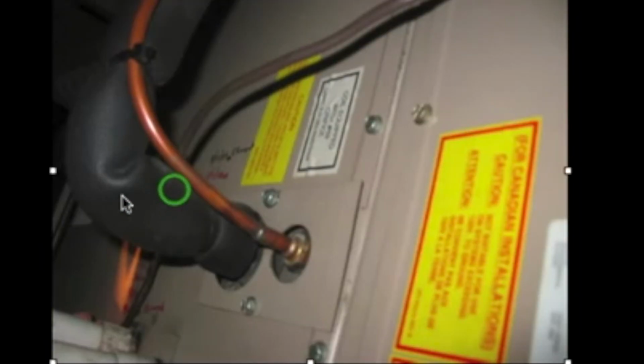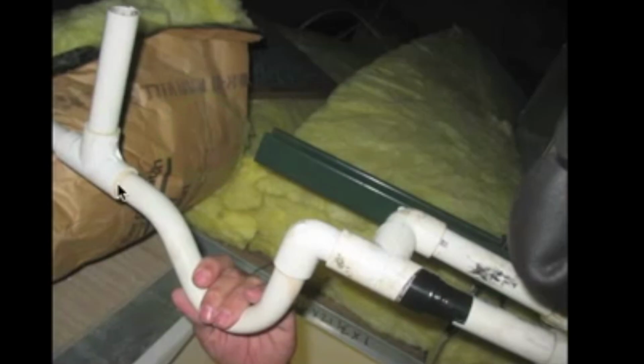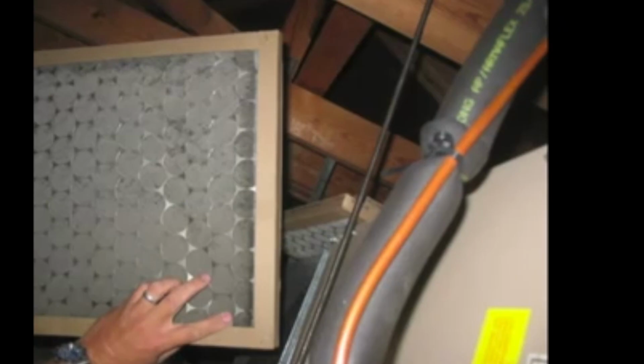This is the other air handler unit. Refrigerant lines. Drainage condensate. Electric shutoff for the coil of the heat pump. Again, no water leak catch pan. Just like a residential unit, I like to have that safety. Should be installed. Disposable air filters are dirty.